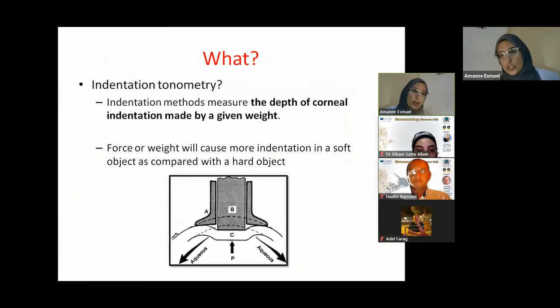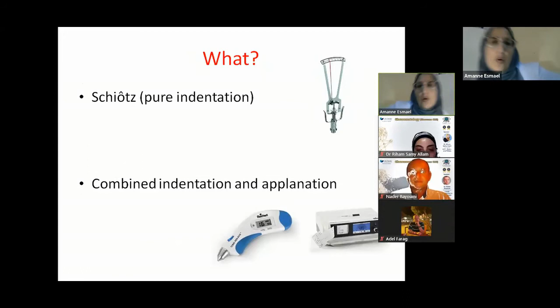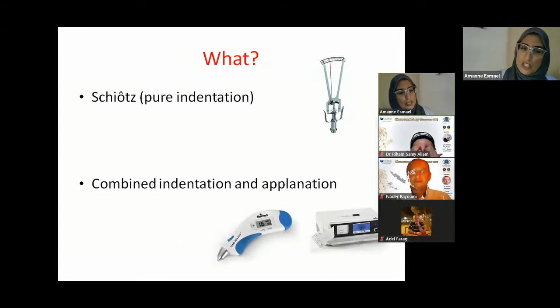So the force or weight that will cause more indentation in soft objects as compared to harder objects will give less indentation. The most commonly used devices right now are either pure indentation devices such as Schiotz, or combined indentation and applanation, as I mentioned before. Schiotz ruled the field of intraocular pressure measurement in the first three quarters or so of the 20th century. And it is a very simple device, easy to use.